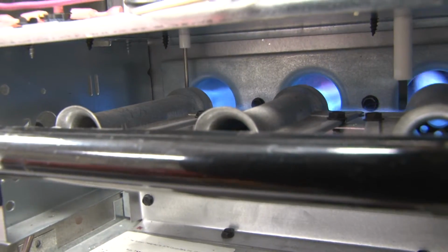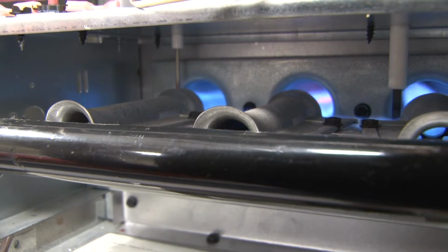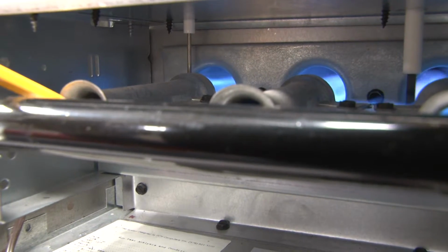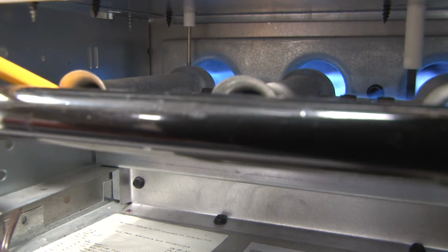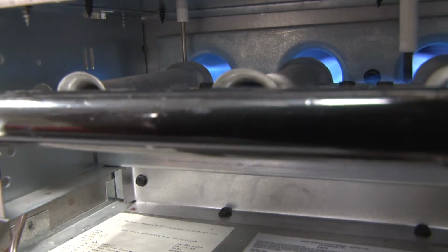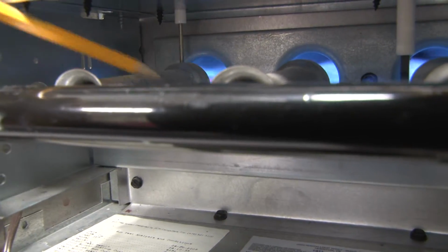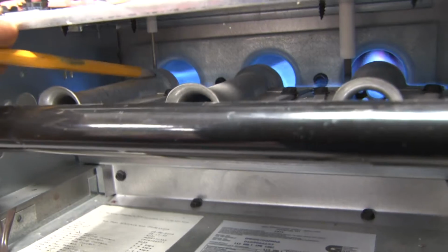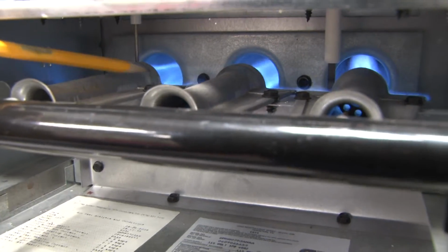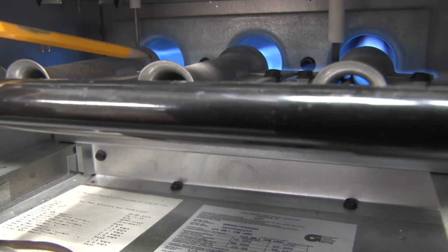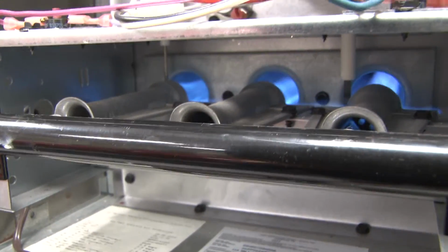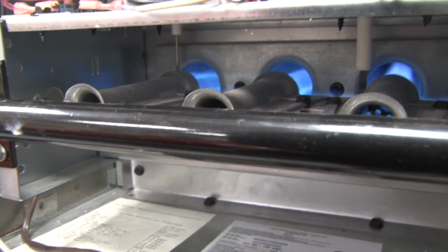Now we see complete combustion using primary air mixing with the fuel. If you notice, I'm moving the pin around the side of where it's mixing. You can see that it is not burning completely because I'm stopping some of the mixture. But as it mixes inside of the burner, it will ignite on the outside, and then it will use additional air, what we call secondary air, to help it burn completely. So complete combustion happens when it's the proper fuel and air mixture.